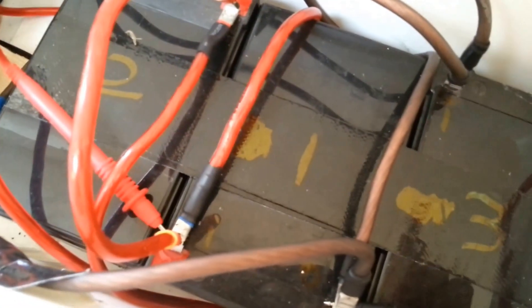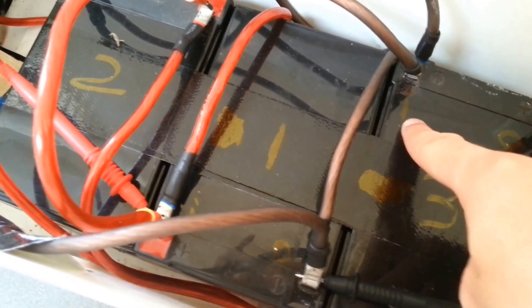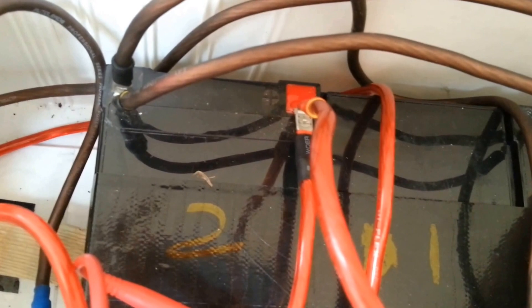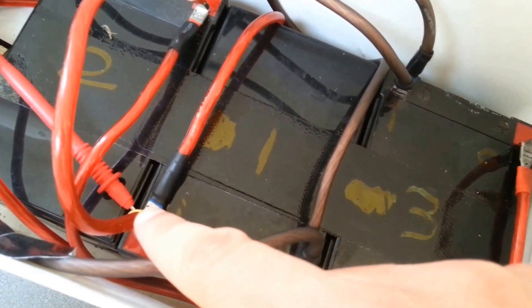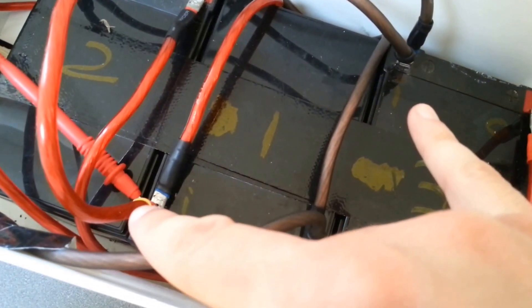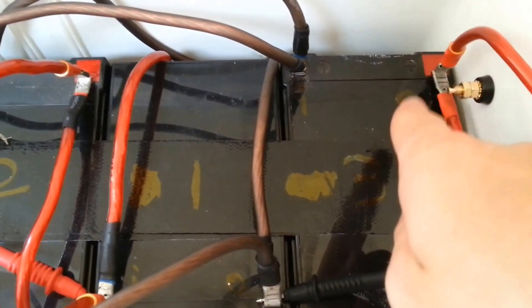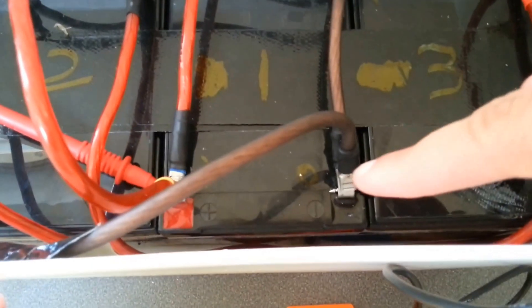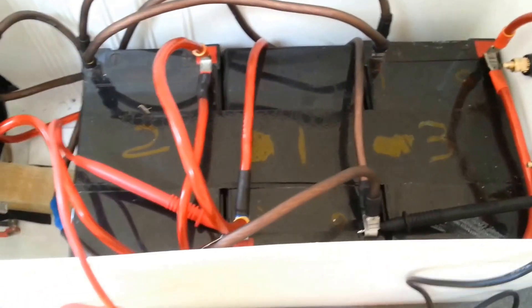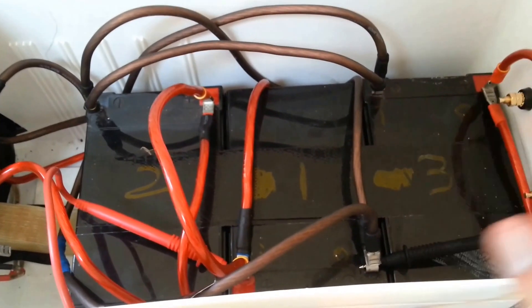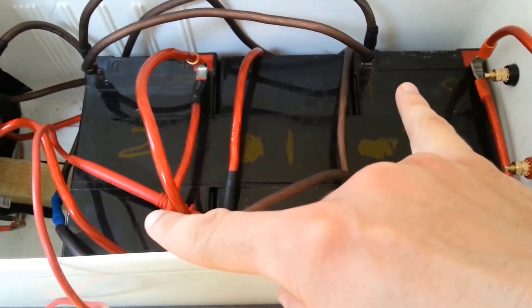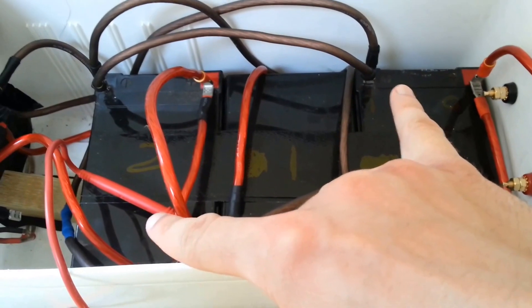So at the moment if you look here we've got input I and O for input and output. The charge comes in on battery three and it also comes in on battery one. Similarly the output comes out of battery three and battery one. So instead of power going in, trickling over, trickling over and coming out, the power is going in across all three batteries equally and out across all three batteries equally.